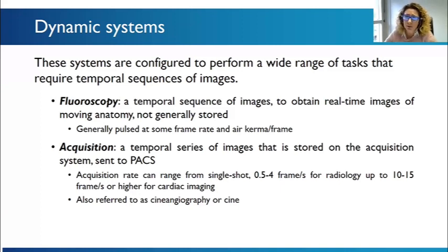The systems are configured in different ways because they have to perform a wide range of tasks that require temporal sequences of images. So we mainly have two types of acquisition. One is called fluoroscopy, which refers to a temporal sequence of images to obtain real-time images of moving anatomy. Normally, fluoroscopy is not stored. Fluoroscopy is nowadays pulsed on most of these systems. The pulse rate and the frame rate vary with the scope of the investigation. It is low normally in peripheral imaging and higher for cardiac imaging. Acquisition, on the other side, which normally we call cine angiography or simply cine, is a modality that we can define as high quality, in which images are acquired and stored in PACS.